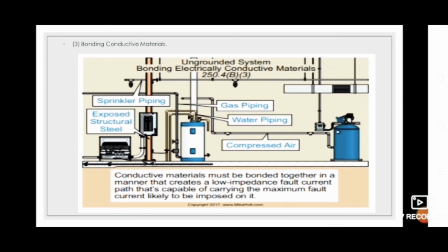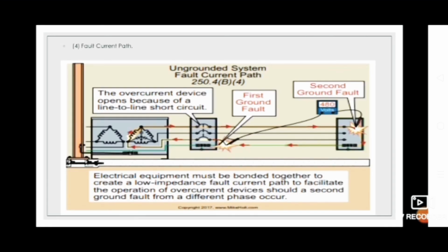This is bonding conductive material. Conductive materials such as metal water piping systems, metal sprinkler piping, metal gas piping, and other metal piping systems, as well as exposed structural steel members likely to become energized, must be bonded together in a manner that creates a low impedance fault current path that is capable of carrying the maximum fault current likely to be imposed on this fault current path.